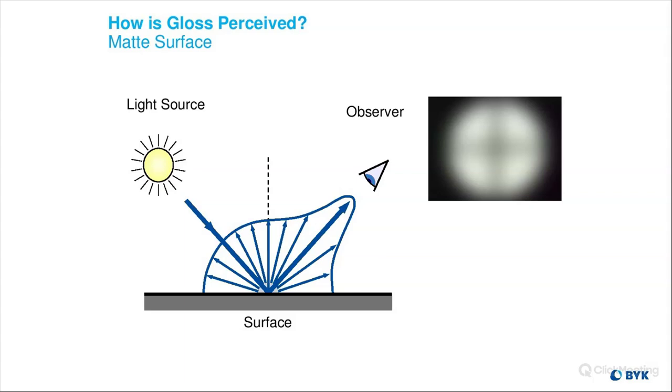Obviously, you have the curvature in that. So we had to use a smaller aperture model that was able to not take into account as much of the curvature, but also create a fixture like Charles was mentioning, so that you can measure in the same location every time, so you're ensuring that every measurement is comparable to one another. So you take into account those practices, which is important.